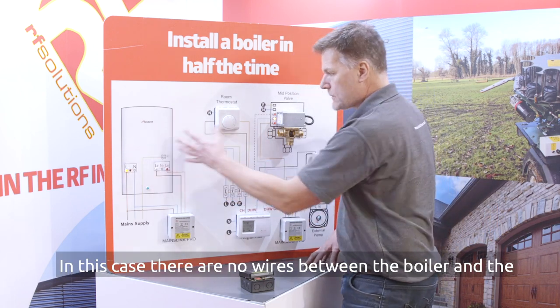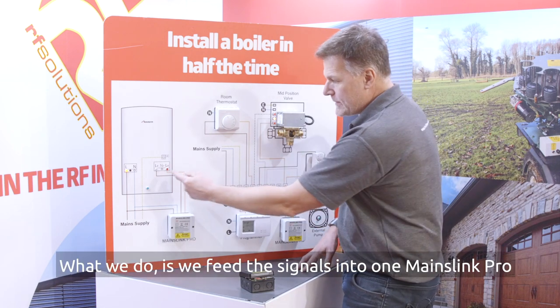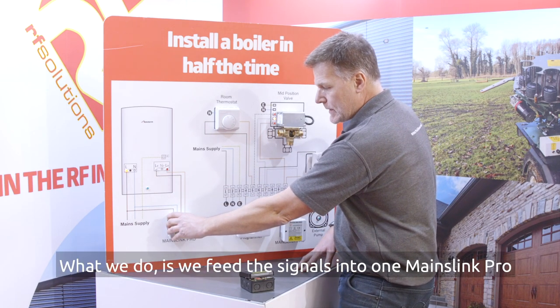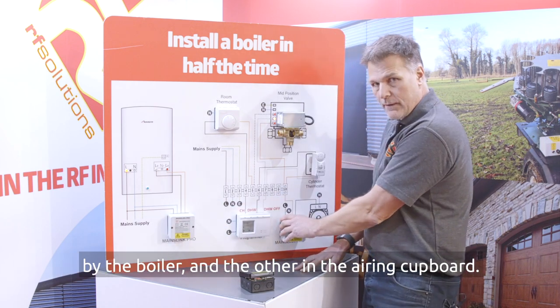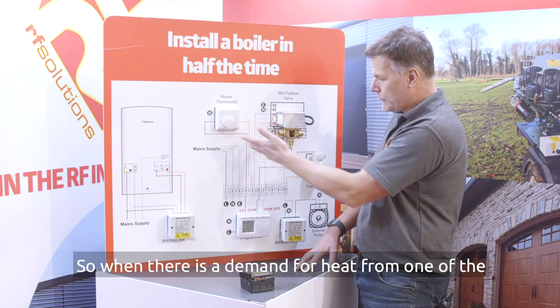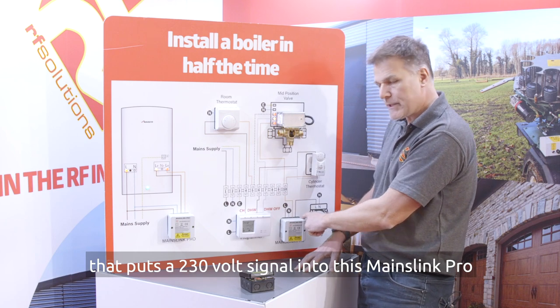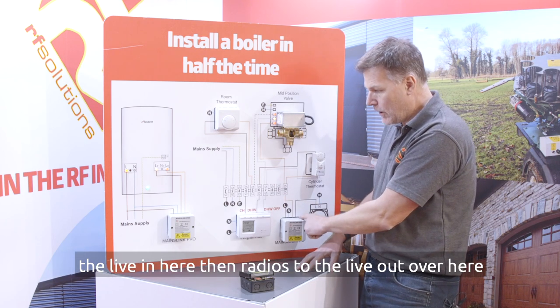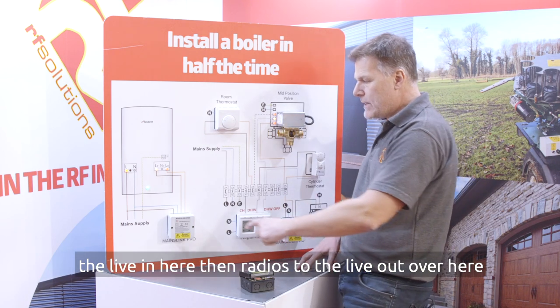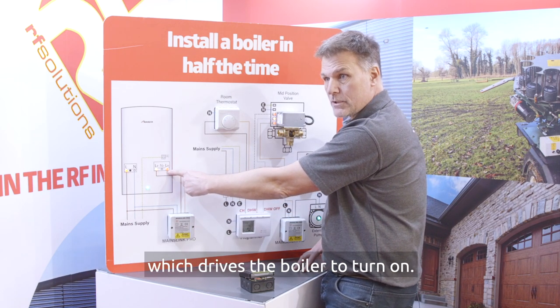In this case there are no wires between the boiler and the wiring centre. We feed the signals into one Mainslink Pro by the boiler and the other one in the airing cupboard. So when there is a demand for heat from one of the sources in the house, if I turn the thermostat up, that puts a 230 volt signal into this Mainslink Pro. The live in here then radios to the live out over here which drives the boiler to turn on.